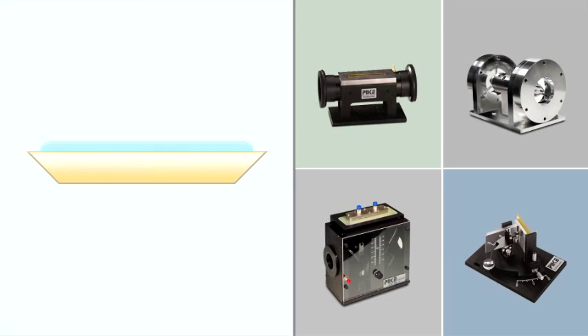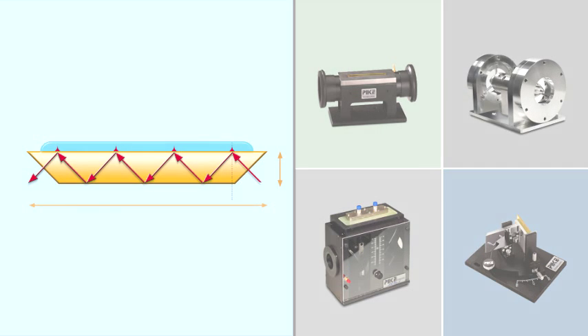For a multi-reflection ATR crystal, the IR beam internally reflects along the length of the crystal. The number of reflections is a function of the angle of incidence and crystal thickness and length.